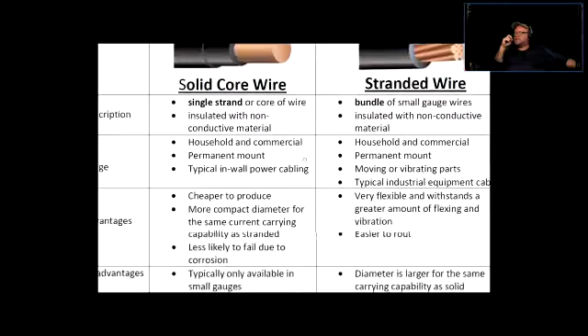Disadvantages of the solid wire - or conductor, I keep calling it cable: it's typically only available in smaller gauges, meaning it should only be so thick. If it gets too thick, then you're not dealing with wire anymore, you're dealing with a metal rod. So solid is not as flexible, and it's harder to handle. Some of the thicker wires, most of the time, you're going to see in the stranded version, just because it's easier to flex, and the thicker the cable gets, the heavier it is to handle.